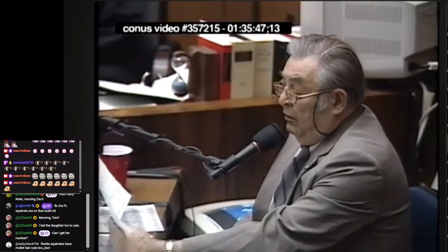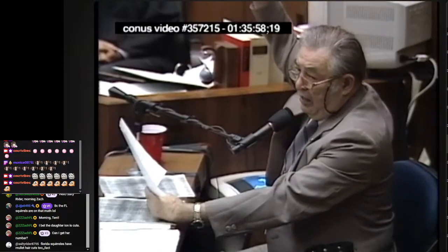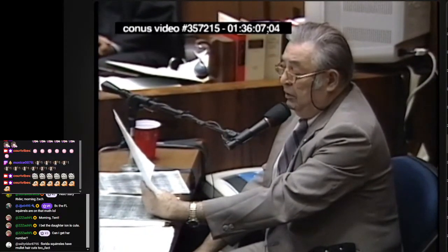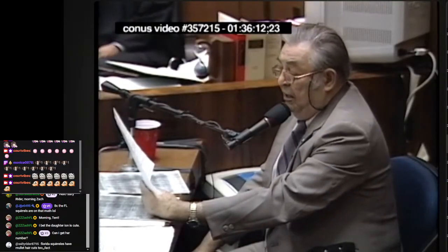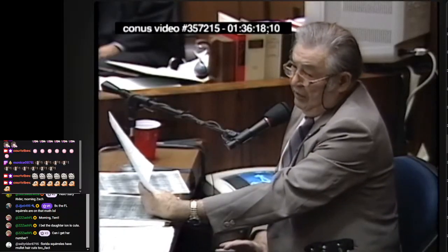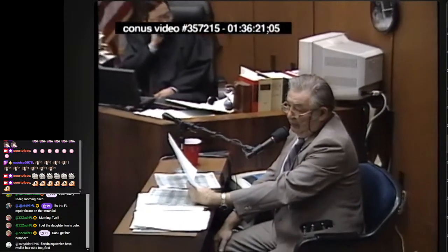Now, the other two numbers right below the 37, what do those mean? The first of these is the detector took in the signals that it got, and it added them all up, and it measured how high a peak was generated from it in counting units. And the height of that peak was 24,223 counting units. The next line, what it does, it makes measurements of all the points in that peak that it can, and gives you an area of that peak.